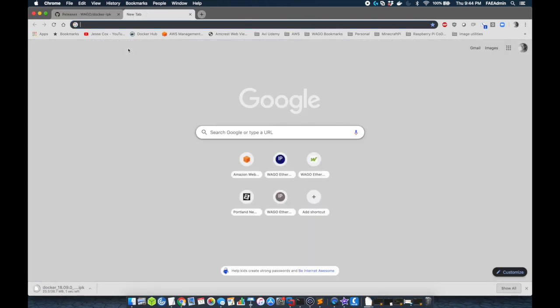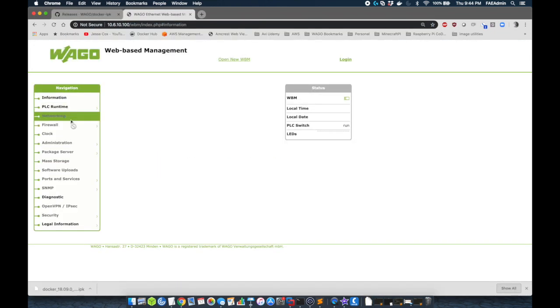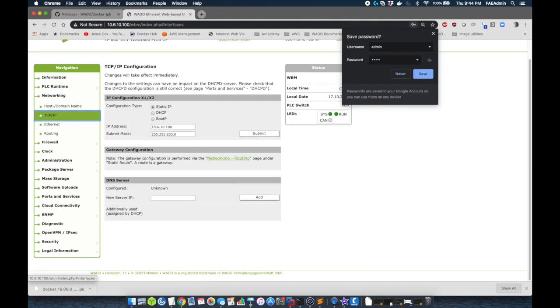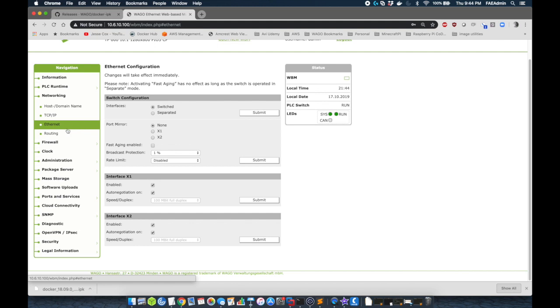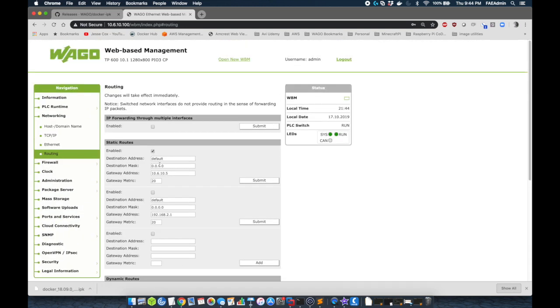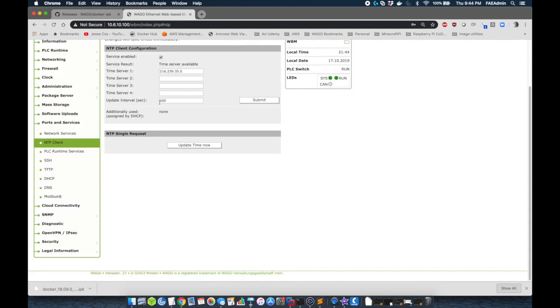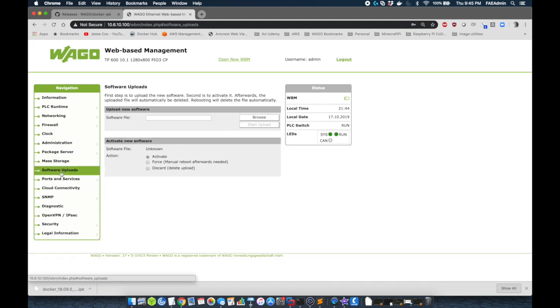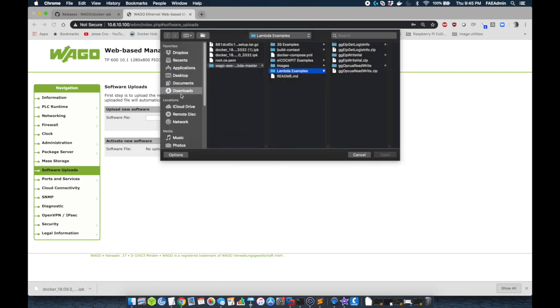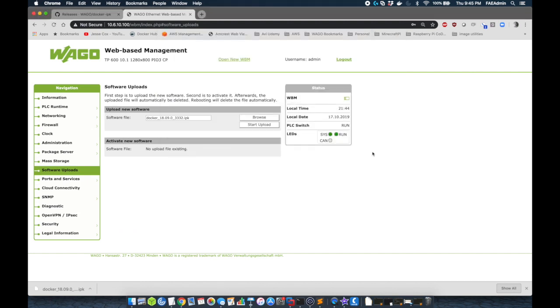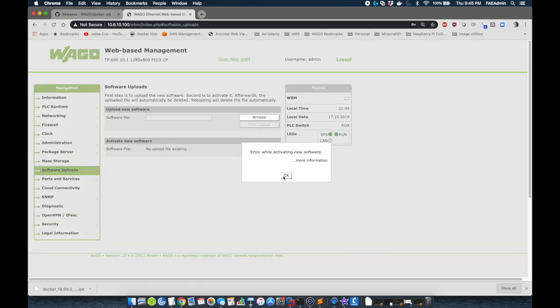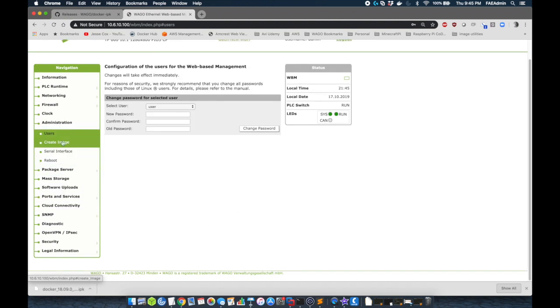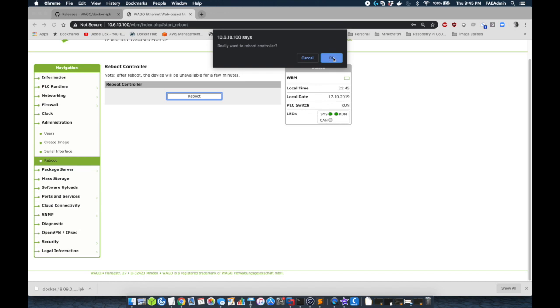Then we're going to navigate to the web-based management of the controller. We're going to just double check some network settings to make sure that we can touch the internet. We want to make sure that we have DNS servers in here. We want to make sure that we're pointed to a router. We want to make sure that our time is correct, and that we have a time server, and that the time zone is also set properly. Next, we can go to software uploads, and we're going to look for that IPK file that we downloaded. We're going to add this. Now mine's going to error because I've already installed this, but we can upload, and then you can activate this. And if it's not installed, you won't get this error. And finally, we're going to reboot the controller.